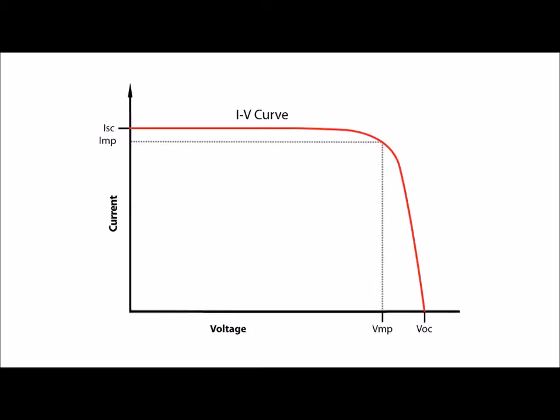The IV curve for a properly operating string is shown here. The height of the plateau varies with the irradiance. The open circuit voltage where current drops to zero varies with cell temperature.